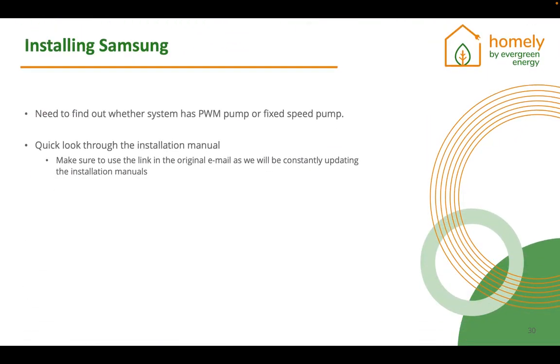On the Samsung, it is important to first identify, before you even buy a Homely, whether you're using a pulse width modulation pump on the primary side or a fixed speed pump. This will determine which kit you actually need to use. We would always advise using the pulse width modulation pump on the Samsungs for improved efficiency of the heat pump. You can find the installation manuals in the email that we'll send through. There you can see how the different installations need to be done.